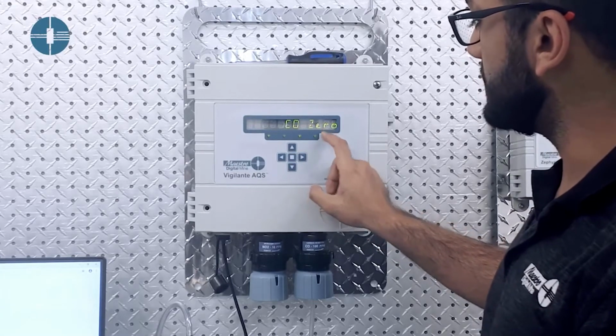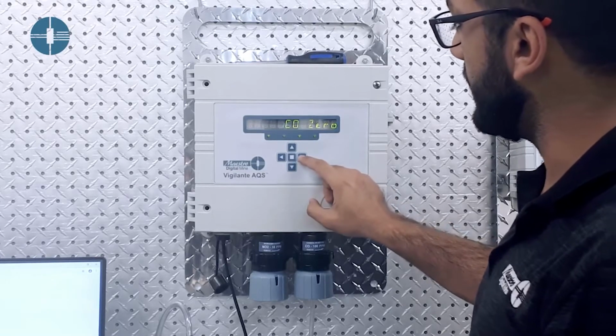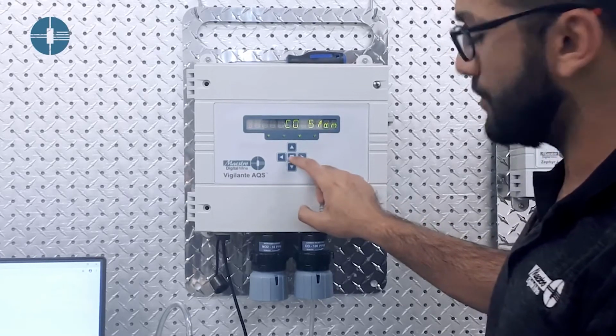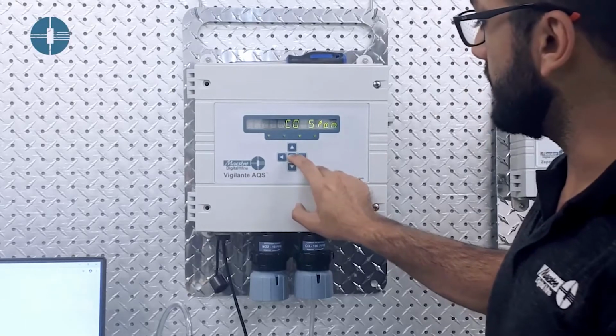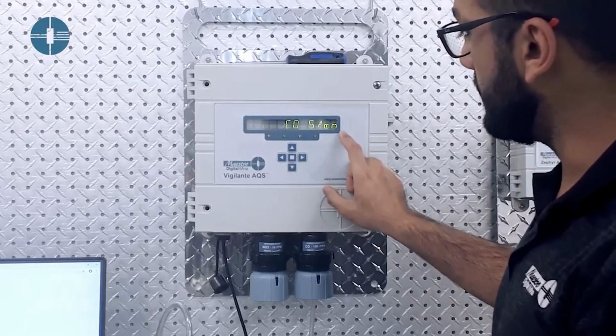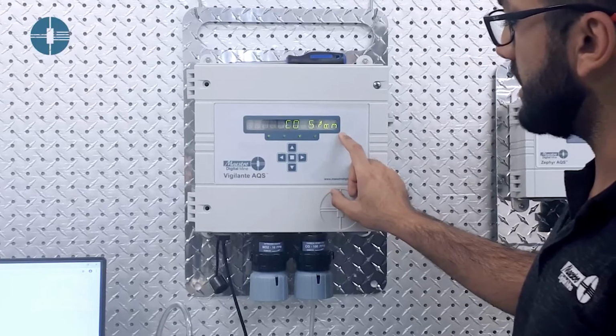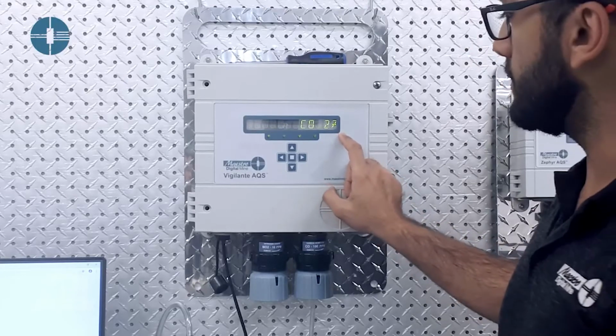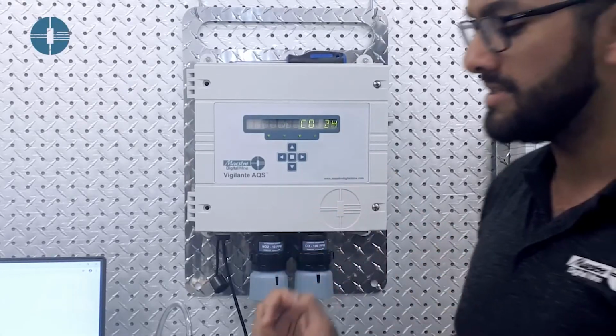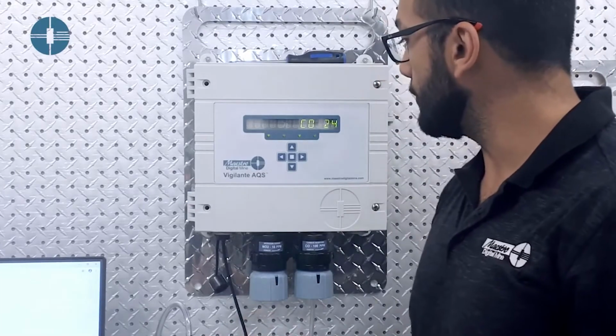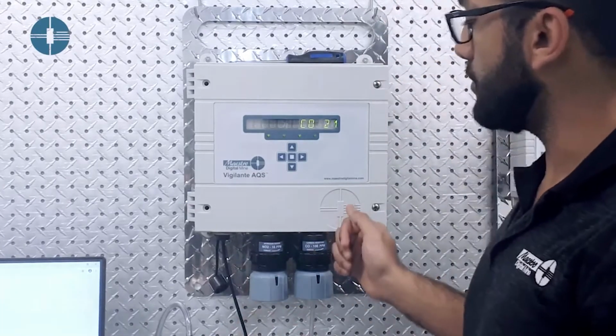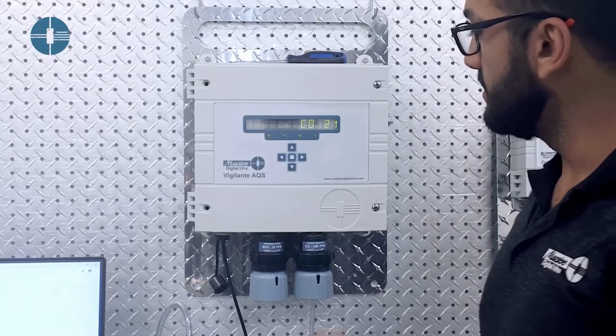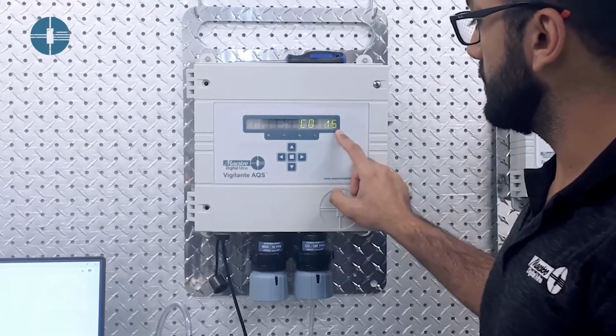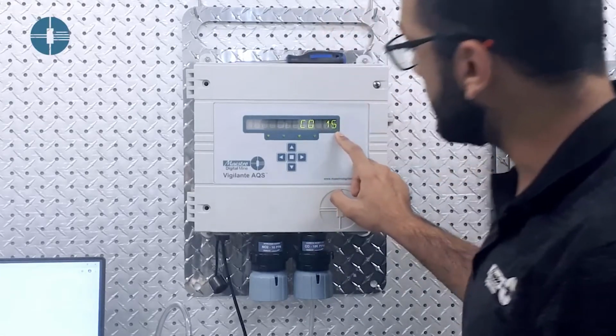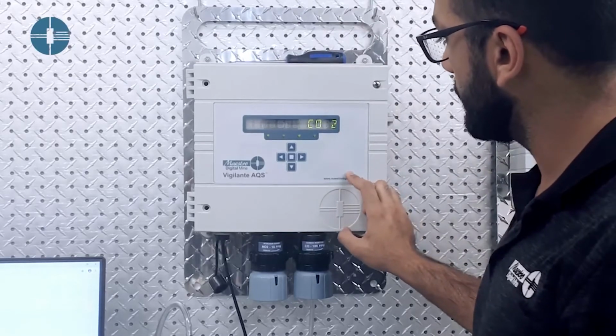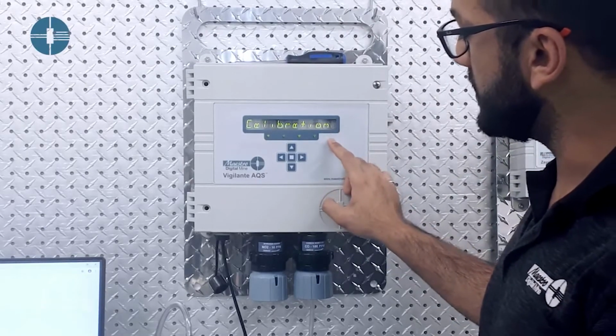So the first time we did 0, but the next, you can hit the right arrow and you can go to span. So once you've hit your 3-minute timer, you're going to hit the OK button there. And it's going to start a 30-second timer, at the end of which it will save the value that the sensor reads, and that will complete the calibration for a Macurco gas sensor. So we're just going to wait another 15 seconds there, and now your calibration is complete.